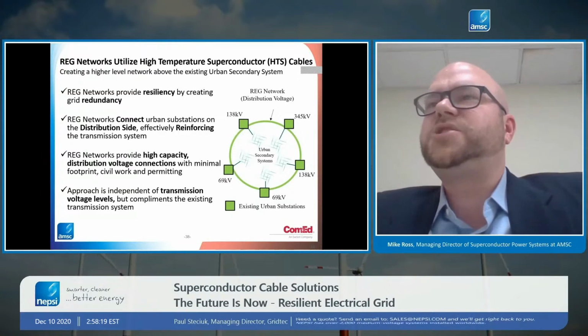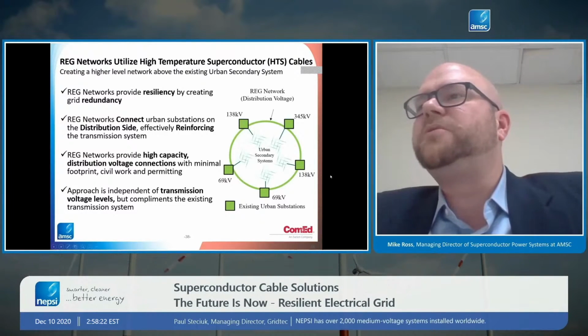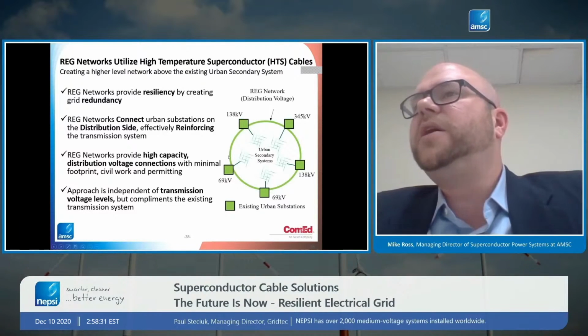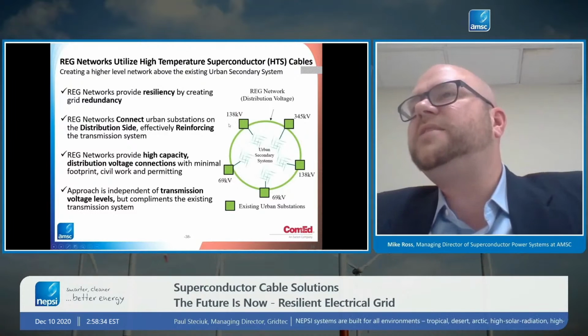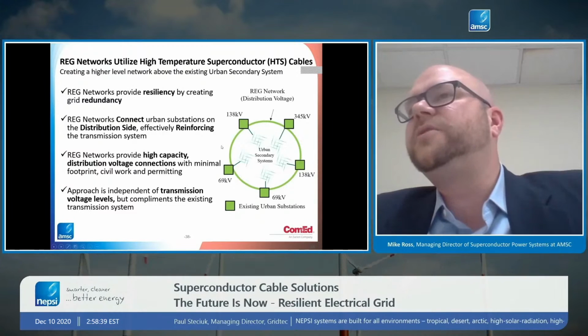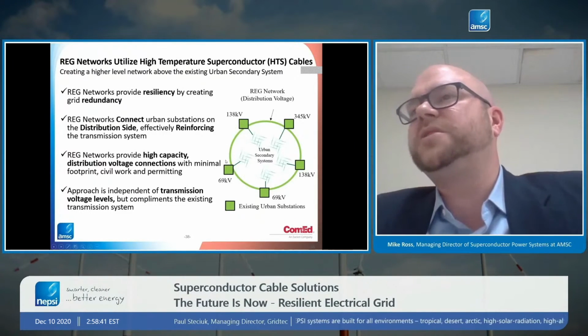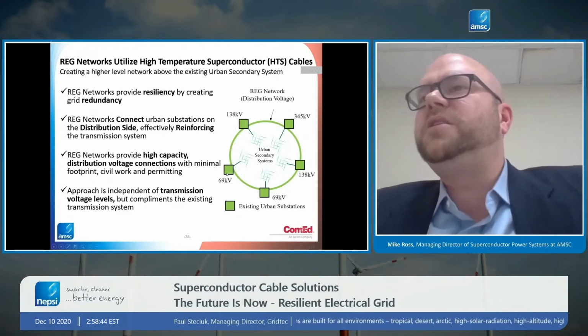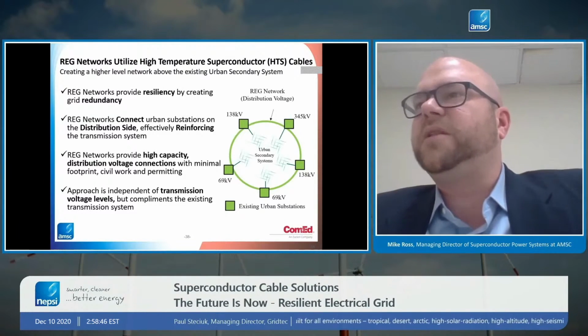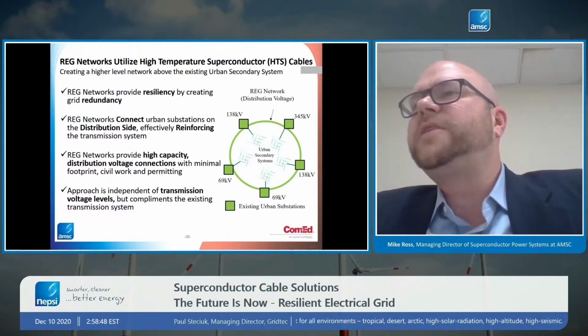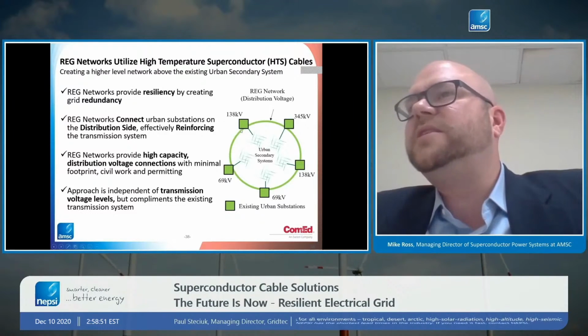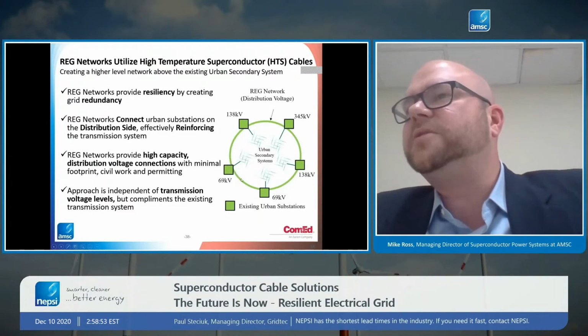The project in Chicago is very, very similar. One of the complications in Chicago is that they have multiple transmission voltages. So there's 69 kV, 138 kV, 345 kV being served by these various utilities in Chicago. So if you were to try to connect these substations together at transmission, it's very difficult because they're at different voltages. So you need big power transformers and things like that. And like any urban utility, Chicago doesn't have a lot of room for equipment like that. So this concept of connecting the substations together at the distribution level is hugely attractive.